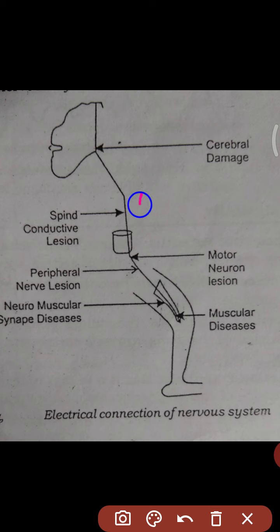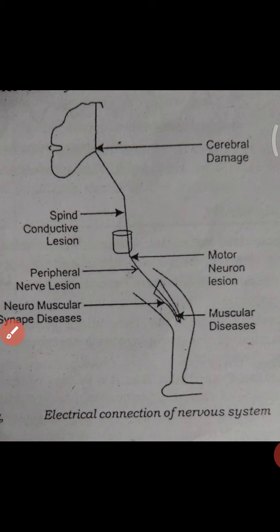For example, the needle electrode is penetrated into the human body, and we give some electrical shock to the particular area where the paralysis is present, using this needle electrode. Then the muscle contracts, and at that time we amplify and observe the audible output on the amplifier as well as the visible information on the oscilloscope in the front panel of the CRO screen. This is the final analysis of the electromyogram.